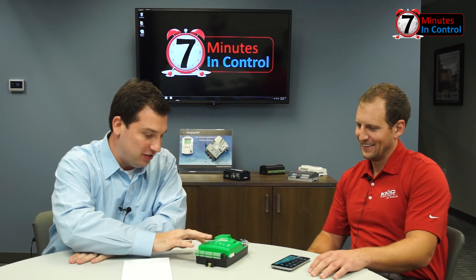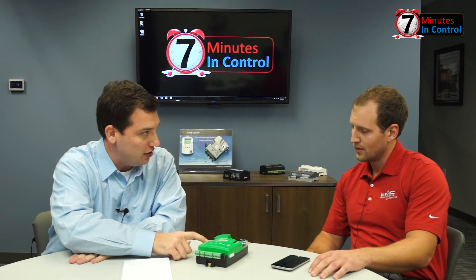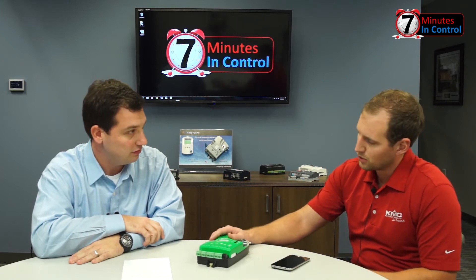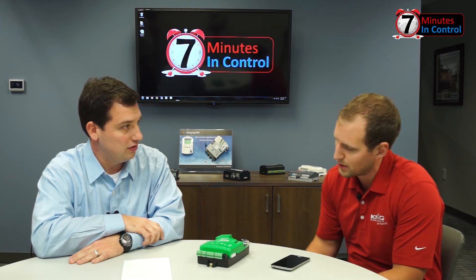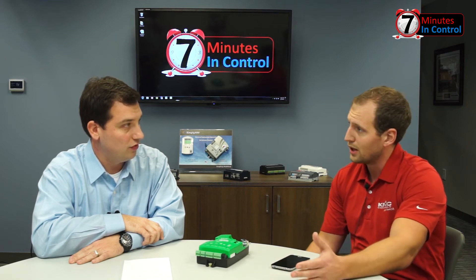These little bulbs — we reference them as network bulbs, or sometimes a network fuse — they're more of a leading indicator if something's wrong. If somebody hooks up voltage to your 485 COM network, or if the phase is off on your transformer, the bulbs glow and that indicates there's a problem in the controller. A lot of times these will blow before you damage the controller if there is voltage put on the network, so it's a safety precaution to help protect the hardware.